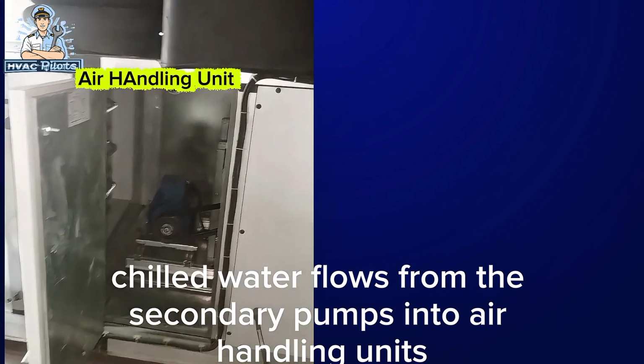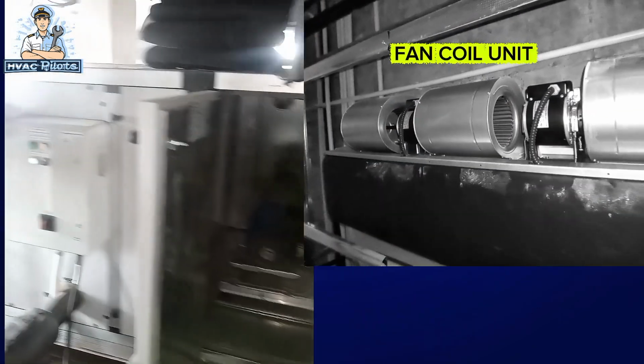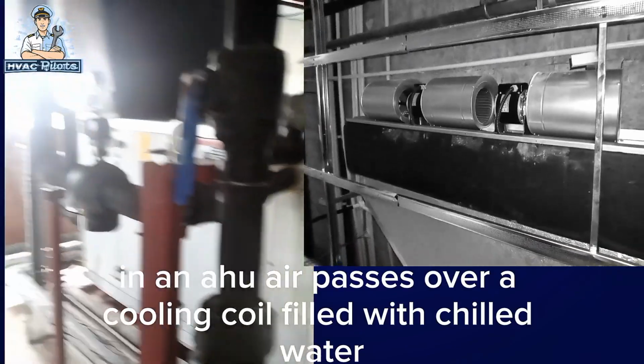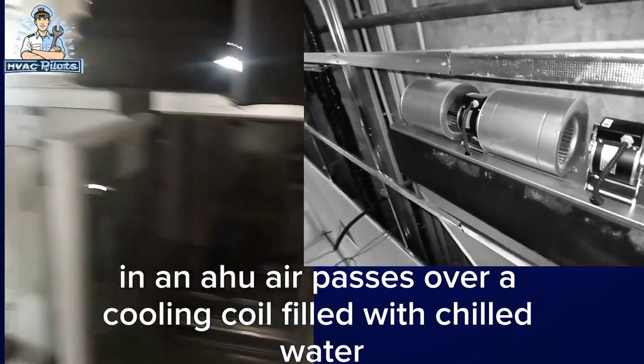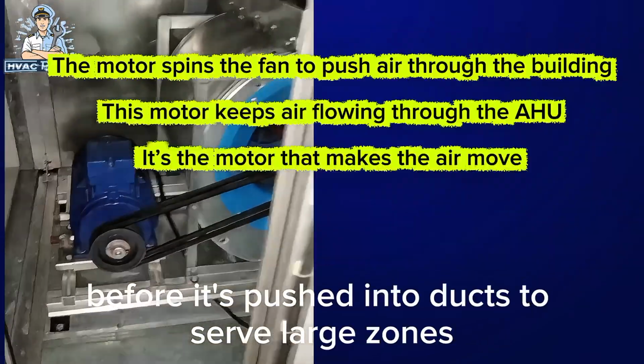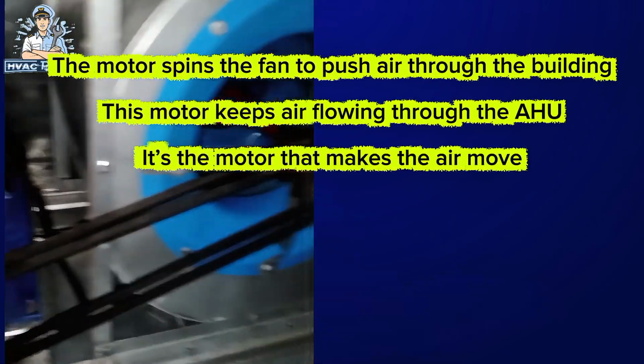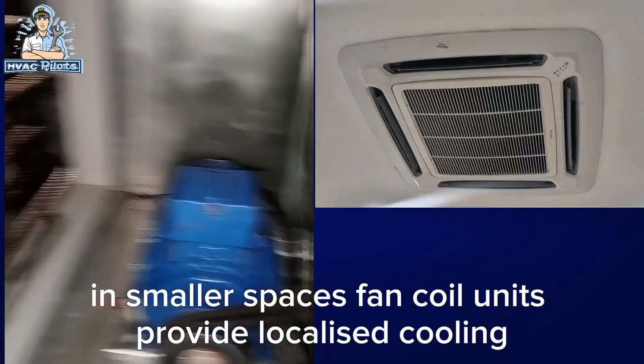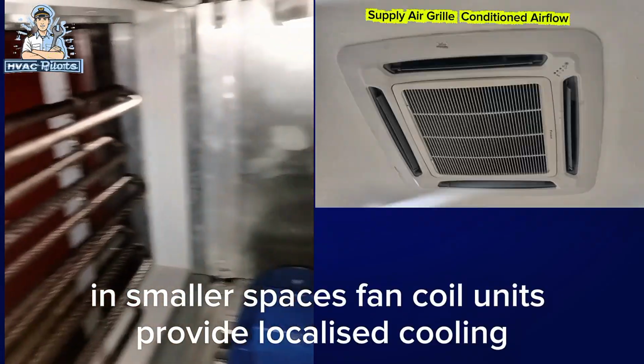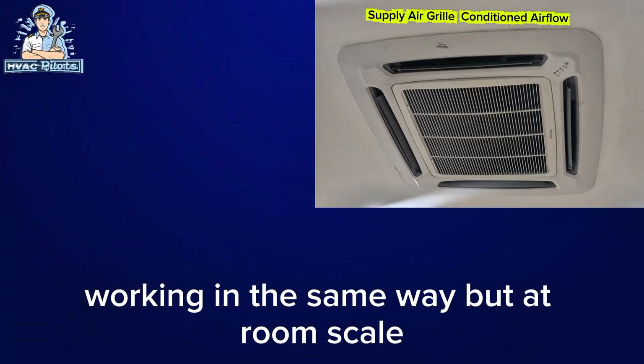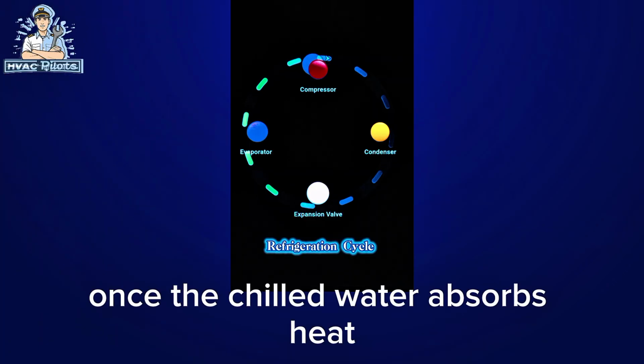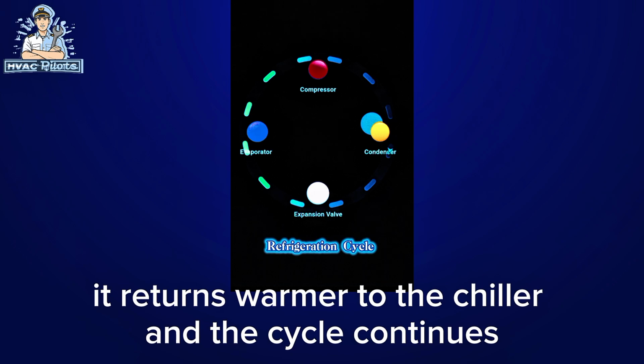Chilled water flows from the secondary pumps into air handling units and fan coil units. In an AHU, air passes over a cooling coil filled with chilled water, reducing air temperature before it's pushed into ducts to serve large zones. In smaller spaces, fan coil units provide localized cooling, working in the same way but at room scale. Once the chilled water absorbs heat, it returns warmer to the chiller, and the cycle continues.